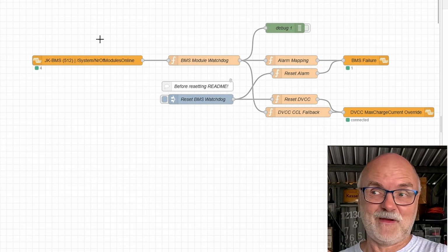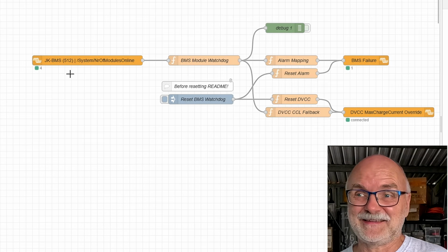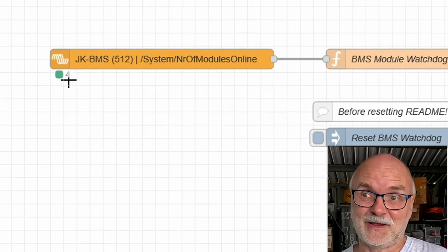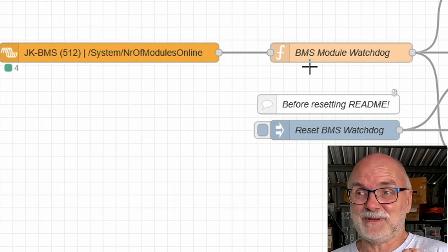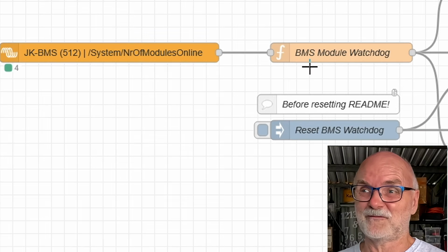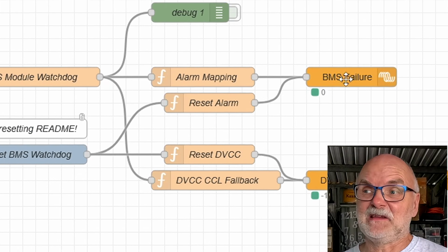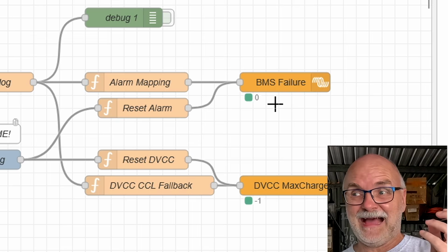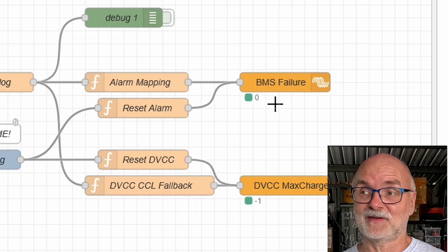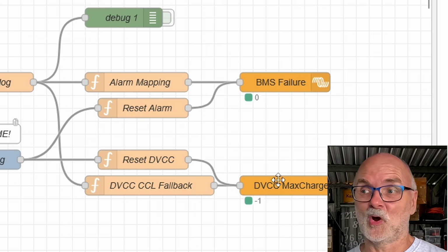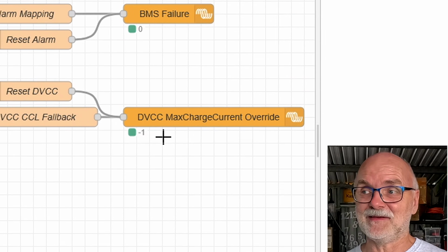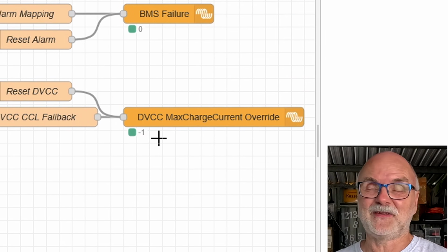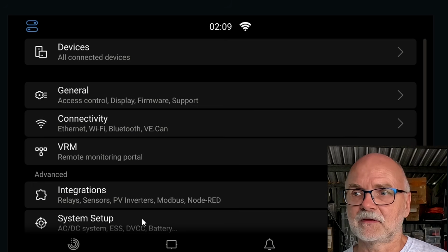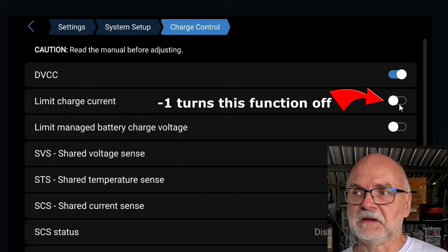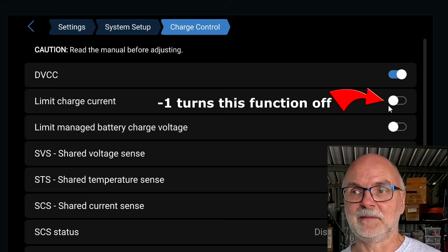So you can see it's a very, very simple workflow. What it basically does is check how many batteries are connected. It has this BMS module watchdog, as I have called it. And here at the end, you can see BMS failure. This is my alarm code I'm sending to the Victron system, and it says 0, so there's no alarm at the moment. And DVCC, the max charge current, so the CCL, is set to -1, which basically turns it off. Settings, DVCC, over here. Yeah, there's no limit. I'm not doing any limits here.